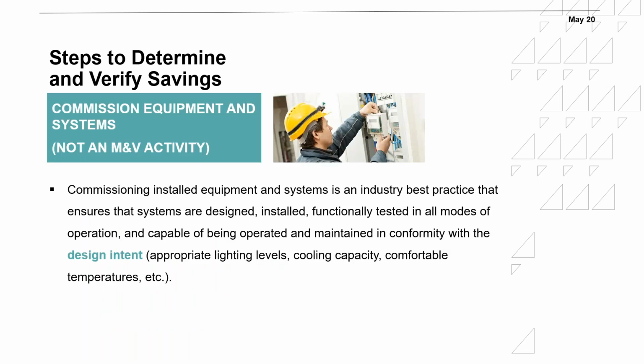Now, this is not part of M&V, but it's definitely a requirement. You need to have proper commissioning for the energy conservation measures to work properly. So you need to commission the installed equipment and systems. In industry best practice, we normally follow ASHRAE Guideline 0 or the ASHRAE Guidelines or Standard 202 when it comes to commissioning. So you need to make sure that things have been installed properly, are functionally tested in all modes, and make sure that savings will be attained. Look at lighting levels, cooling capacities, kilowatt per ton, all these things need to be done. Now, that's not part of M&V, but it's recommended and it's required basically to make sure that savings will be attained. It's not an M&V activity.